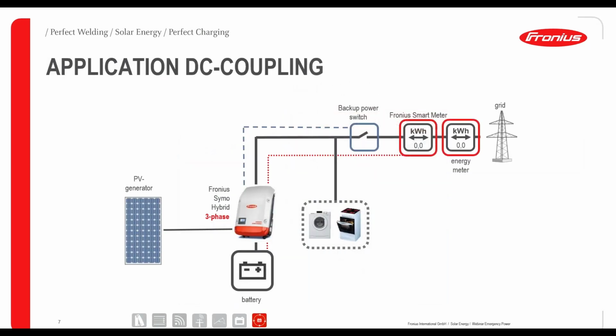Then I'll continue with the first basic explanation about our system. Our system is a so-called DC coupled system. Basically, we have the hybrid inverter, the Fronius Symo Hybrid 3-phase inverter, the PV generator, a battery, and then you supply your loads, and after that we have the backup power switch. When there's a blackout, let's say, this switch needs to switch over and of course isolate the system from the grid.